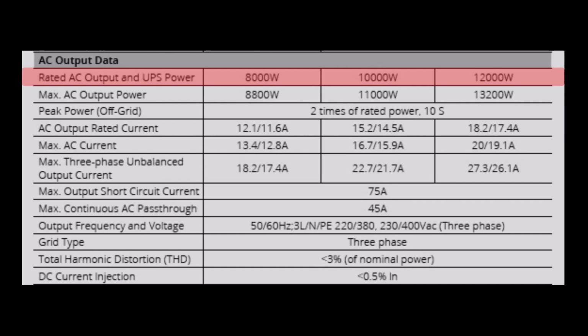Okay, so let's have a look at the alternating current output data. And this unit is rated as an output of 12,000 watts. UPS stands for uninterrupted power supply. So it can run at that comfortably for hours. The maximum AC output is 13,200 watts. This just allows for unexpected surges and stuff, but it could run at that, but probably stresses the unit a little bit.